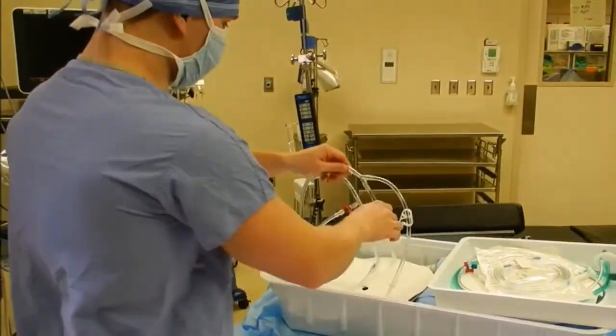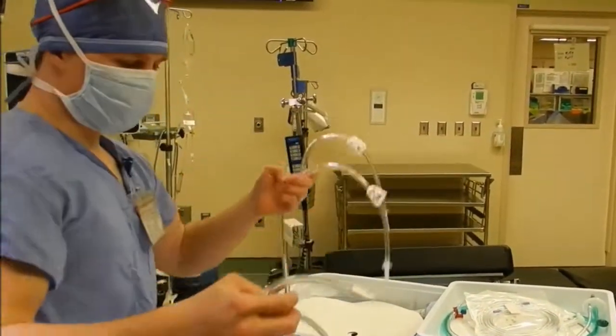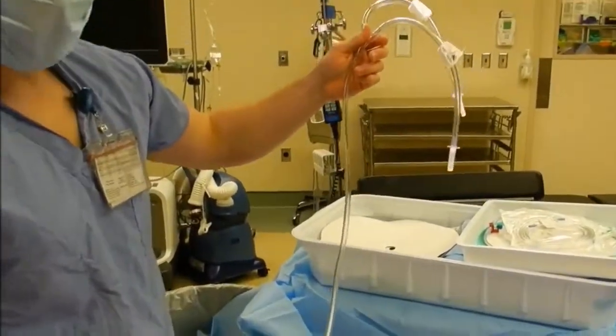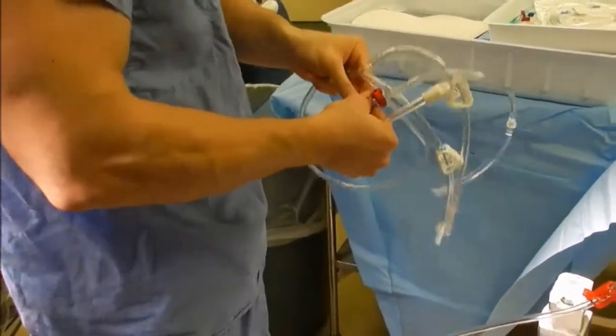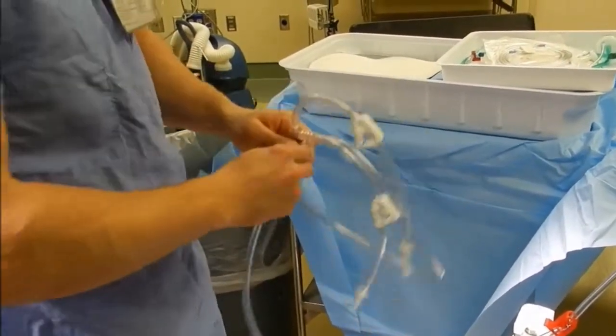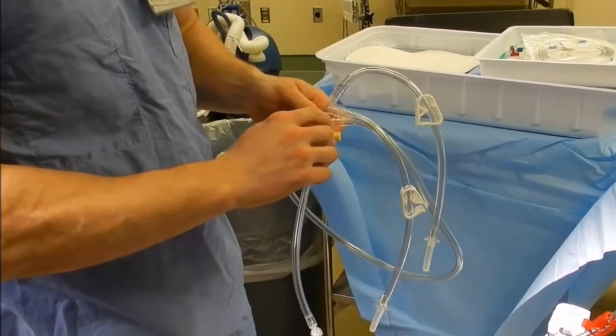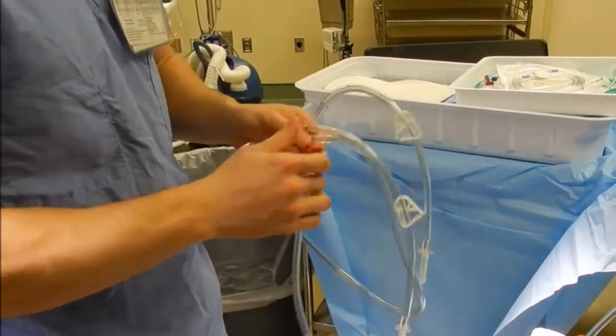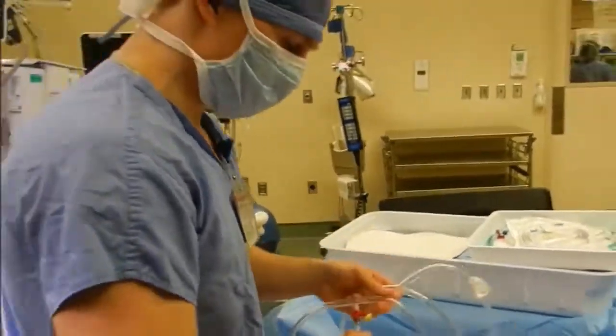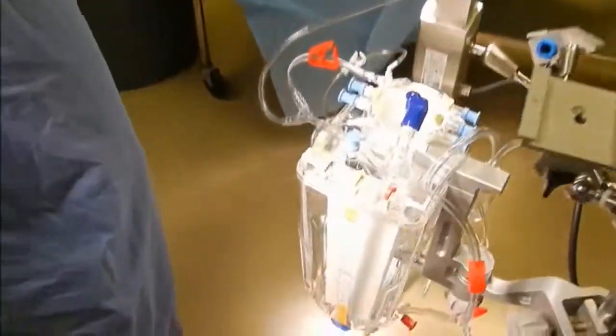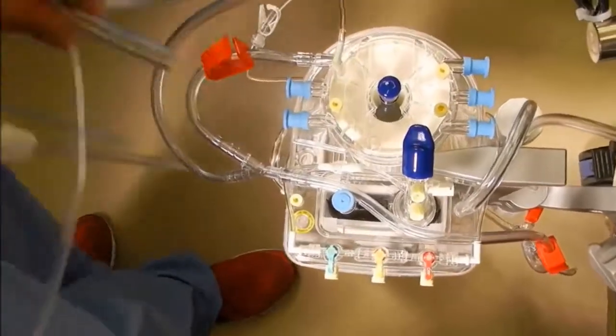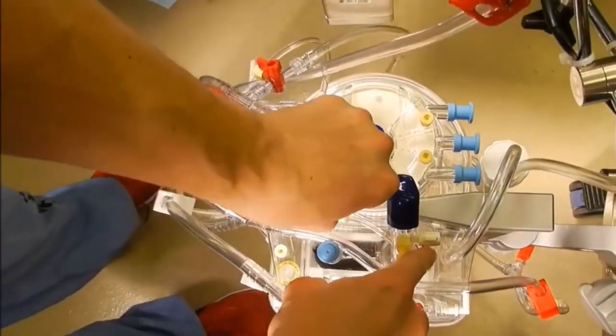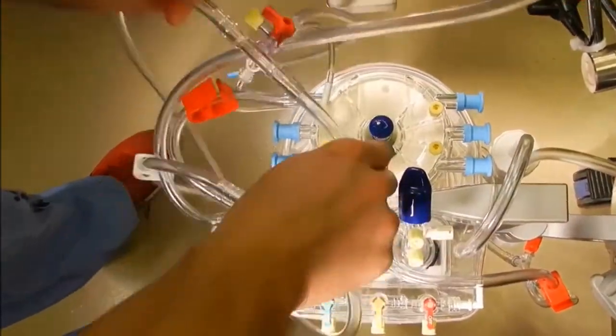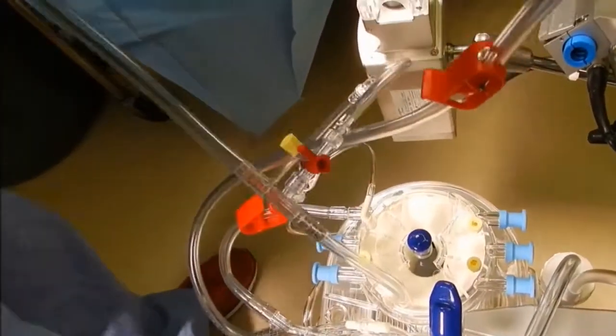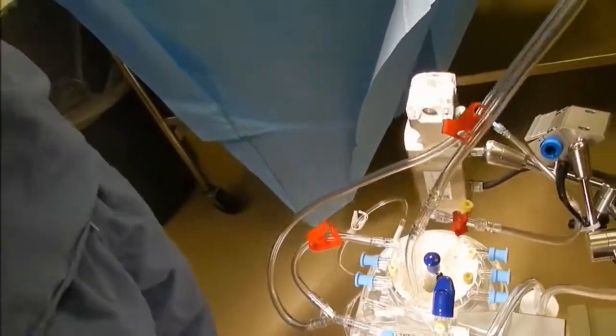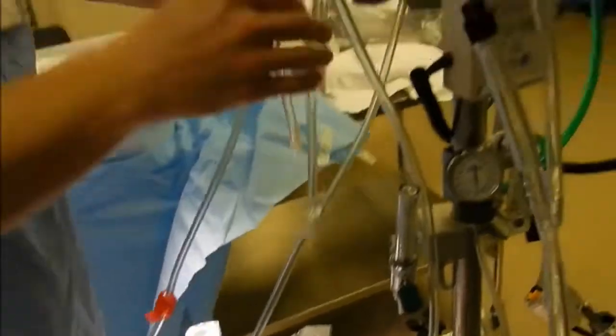Dividers, which separate different pieces of our circuit. This is our quick prime line / bailout shunt, as I like to call it. It's our only shunt that appears after the integrated oxygenator / arterial filter, so it's used to remove any air that might make it past our oxygenator. It goes where it says, quick prime line to quick prime connection. I orient the shunt this way where our arterial line will stand. I just hang this up like so.